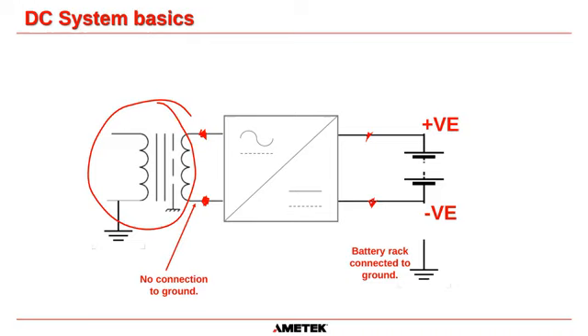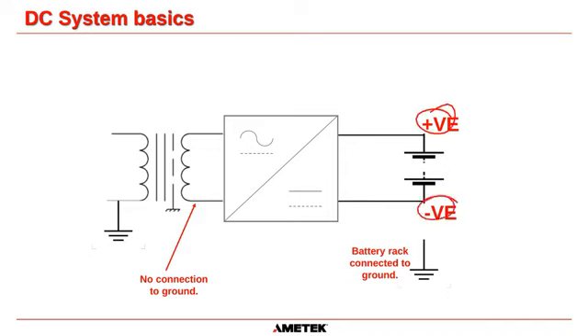Now, as we go down through these slides, we do introduce a path to ground, or a connection to ground, so we can detect ground faults, and we'll discuss how that's done in a little bit. But what you've got to understand is, yes, these batteries may be, and actually will be, mounted on a rack. And that rack will be metal, usually metal that's been covered in some kind of insulation, whether plastic, rubber, whatever it is, to prevent an actual connection to the ground. But the batteries will be mounted on a battery rack, and the metal of that rack will be connected to ground. But the battery positive and the battery negative themselves have no connection to ground whatsoever inside a properly designed industrial charger rectifier that has an isolation transformer. Okay.